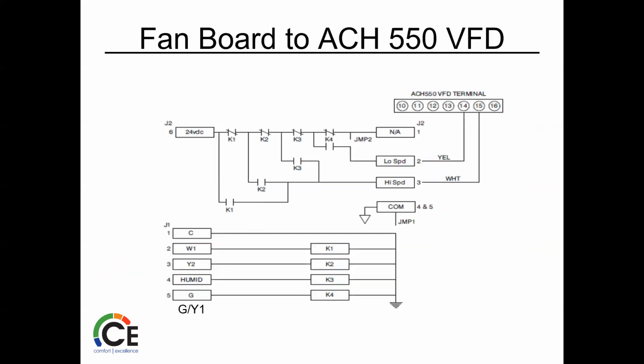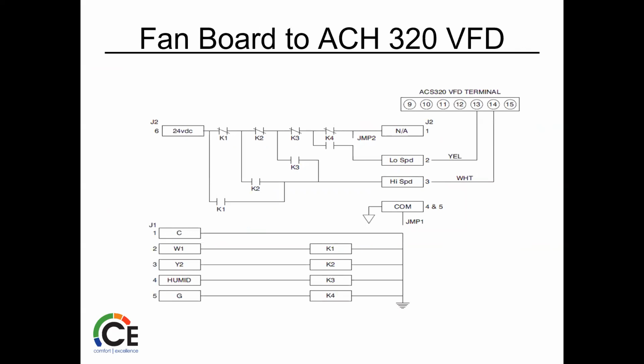It's just a duplicate, so let's skip to this one. Again, we showed the 550 before. Same thing here on this 320. The number 5 input is for fan or Y1. It energizes and opens this upper relay, closes the lower relay, and energizes the yellow wire to get you low speed operation. That's 66% or 40 hertz at that point.